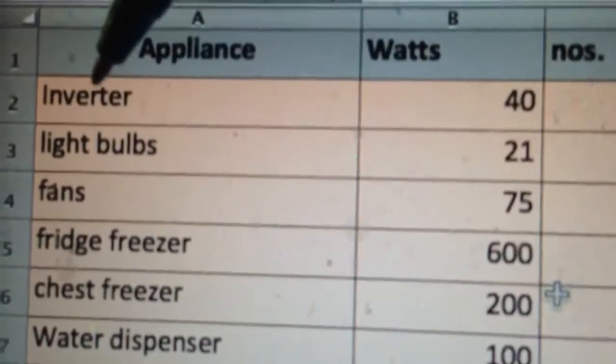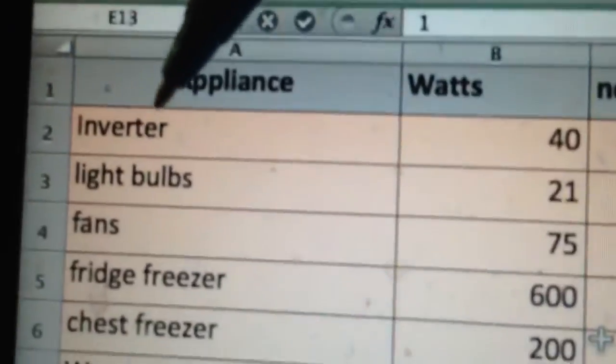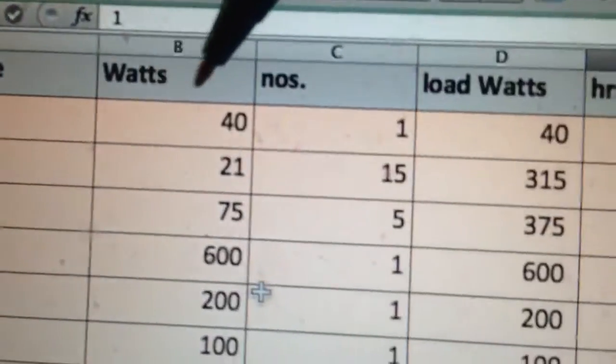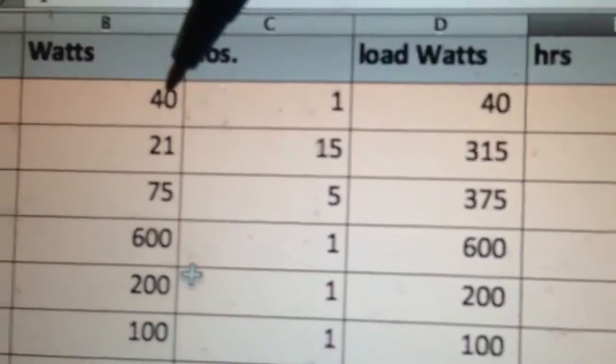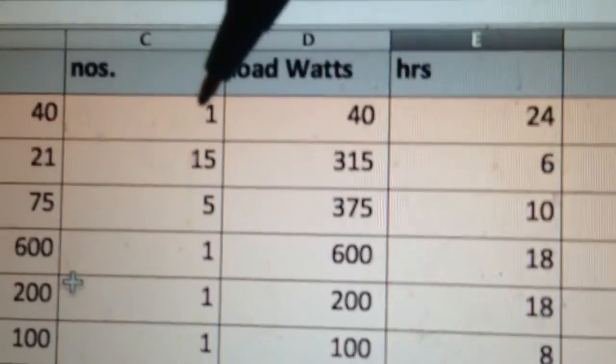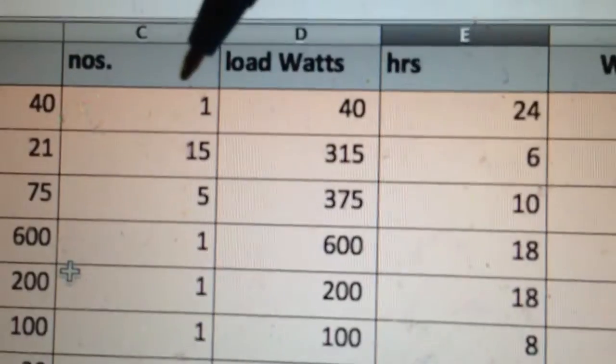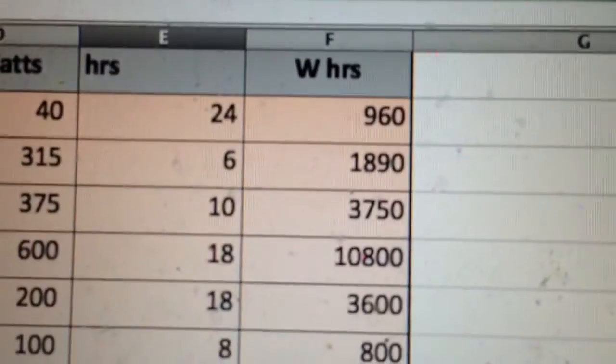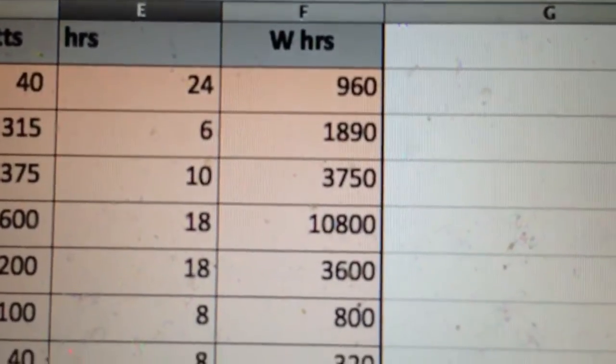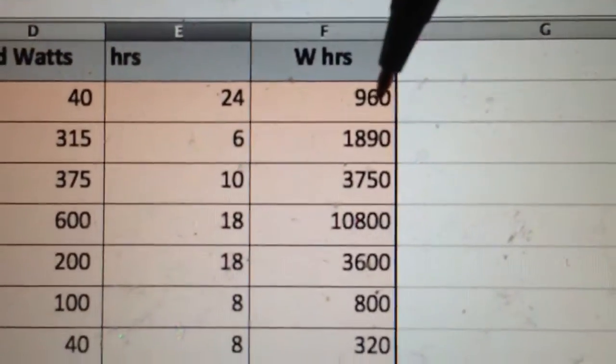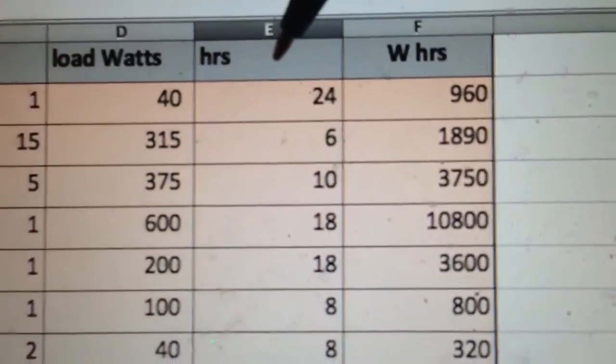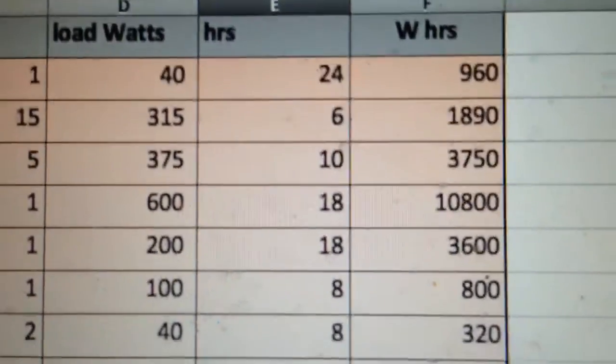For example, the inverter. Always start with your inverter because people often forget the inverter's an appliance. The inverter, my battery, consumes 40 watts. It's a high frequency inverter. I've got one of them. It's on for 24 hours a day, so it's 960 watt hours. So that's pretty much the idea.